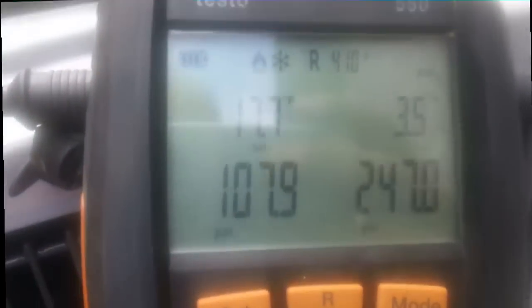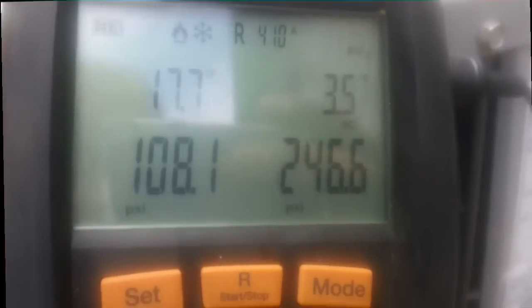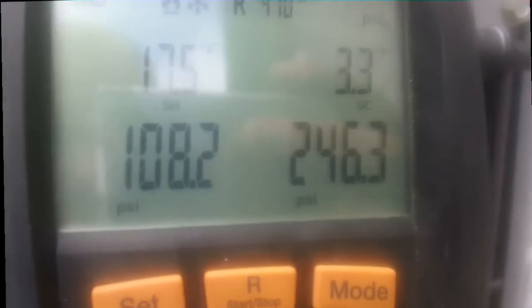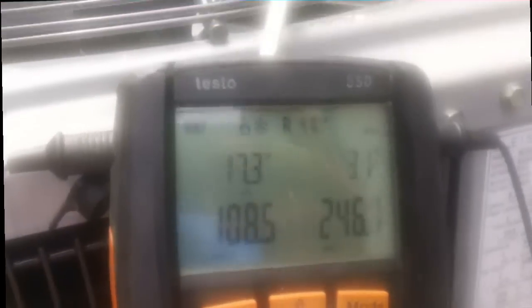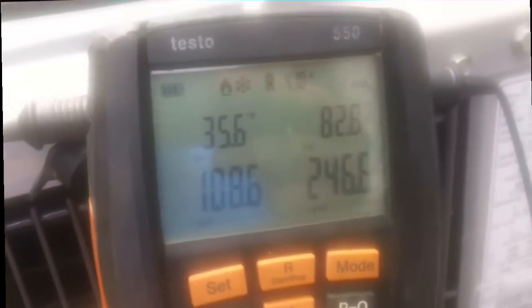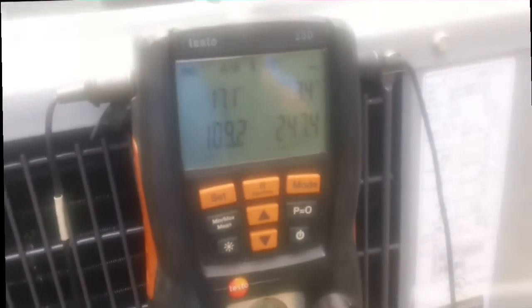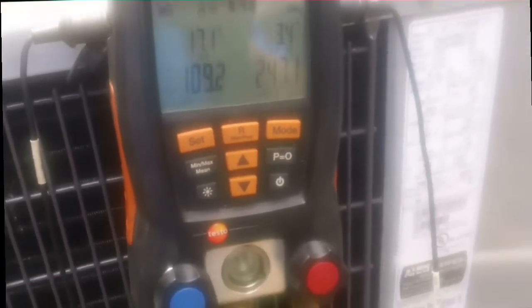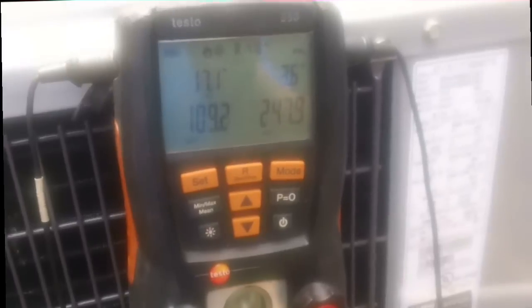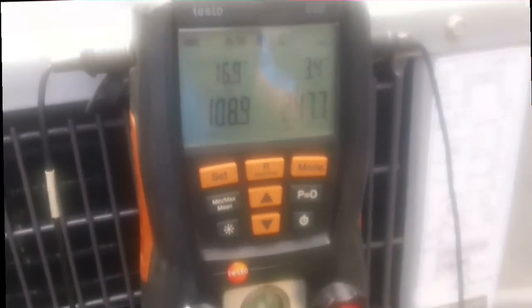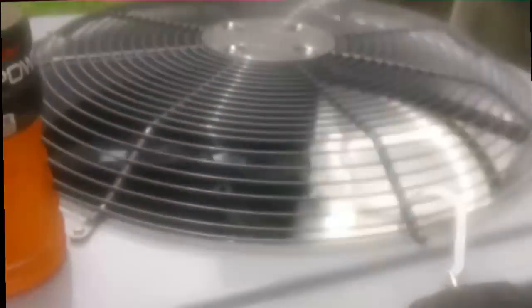All right guys, we're running. The target superheat was 16, we're running at 17, that's perfect. The head pressure looks good, suction pressure looks good. Good thing I went and checked that piston and changed that piston. So guys, if you're ever doing mobile homes or anything and you're changing just the condensing unit, doing a conversion like I did here, always go check your metering device. Make sure your piston size is right, because if I'd have left this thing on that 96 piston, it would have been a disaster.